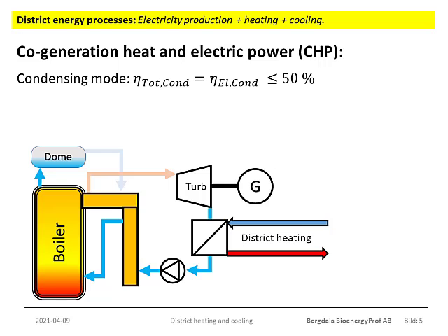So the lower the district heating network return temperature, the higher the electricity efficiency. But the electricity efficiency will always be lower than what can be achieved in condensing mode. The positive thing with this case is that the heat losses from the condenser have now been turned into a commercial product. So you lose a bit of electricity, but you gain a new product. And that will in turn improve the total efficiency.